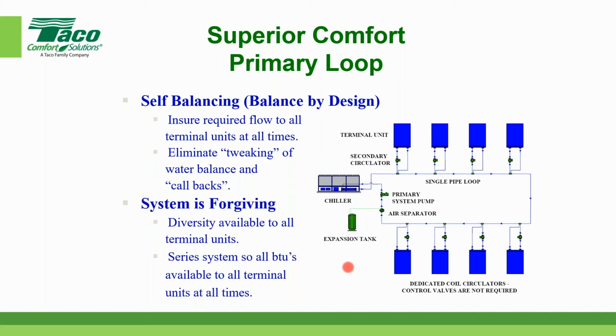But anyways, I digress a little bit. If you have a heat pump system, you're going to stay within that 70 to 60 or 60 to 90 degree temperature range, and that cascade doesn't really affect the output of the heat pump, right? You put in a 2-ton heat pump, and if you have 60-degree water or 80-degree water going in there, you're still going to get the BTUs that you're expecting in the room that you've designed for, right? So just kind of think that through a little bit.